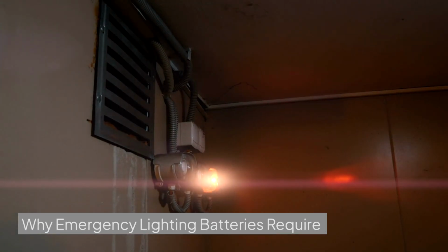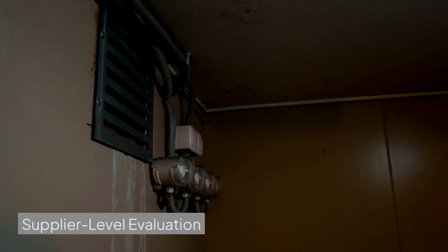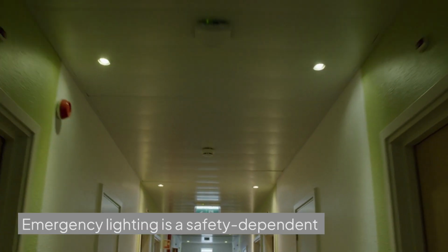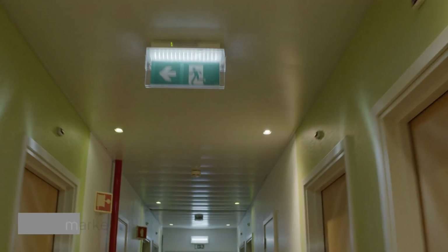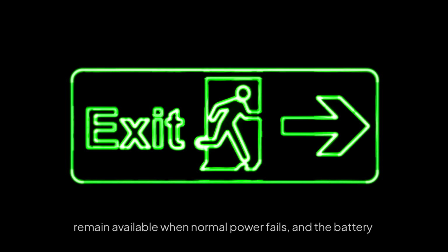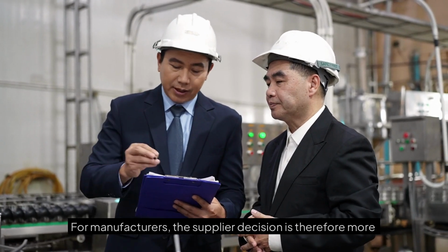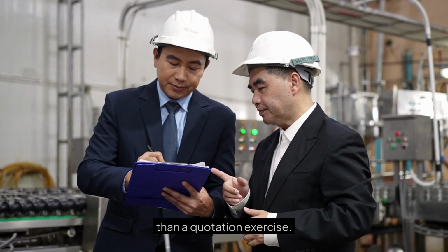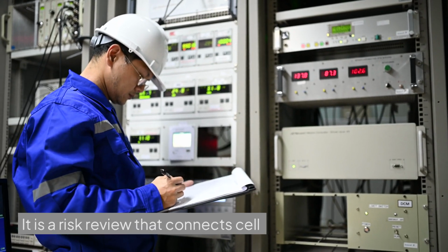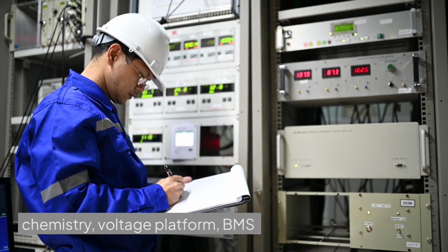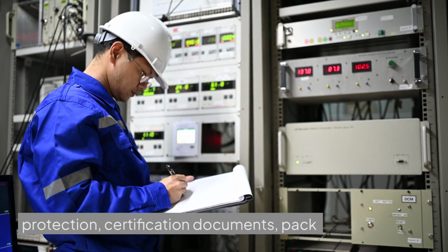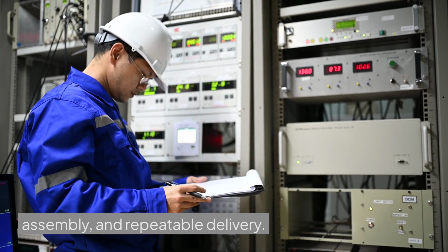Why emergency lighting batteries require supplier-level evaluation. Emergency lighting is a safety-dependent product category, not a simple accessory market. Exit signs, fire lights, and central emergency systems must remain available when normal power fails, and the battery pack becomes the hidden component that decides whether the system can deliver its designed runtime. For manufacturers, the supplier decision is therefore more than a quotation exercise. It is a risk review that connects cell chemistry, voltage platform, BMS protection, certification documents, pack assembly, and repeatable delivery.